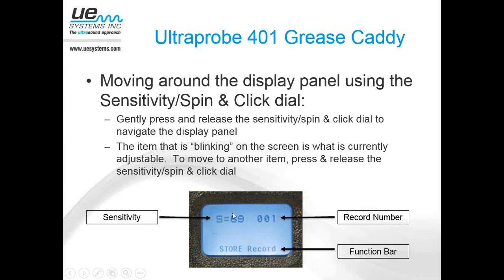So if we're currently adjusting sensitivity and I want to get over to the record number, I just simply press and release the sensitivity dial, and that's going to move me over to the record number. If I press and release again, that's going to move me down to the function bar, and there I can scroll through some of the different functions, some of the different menus. And then if I press and release again, that's going to bring me back to the sensitivity. So again, the press and release of that sensitivity dial is what's going to navigate me around the screen.